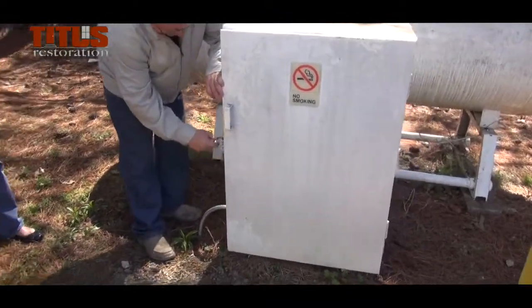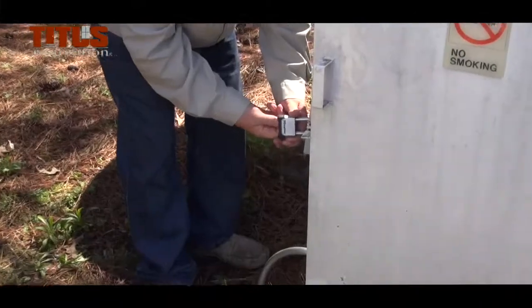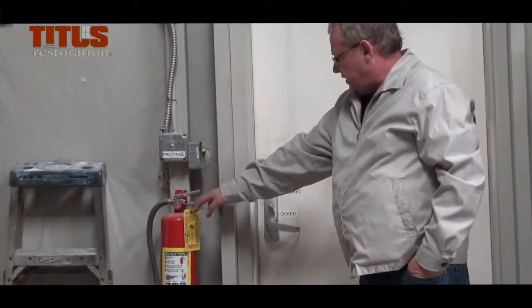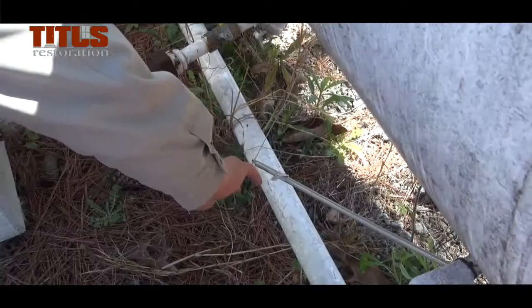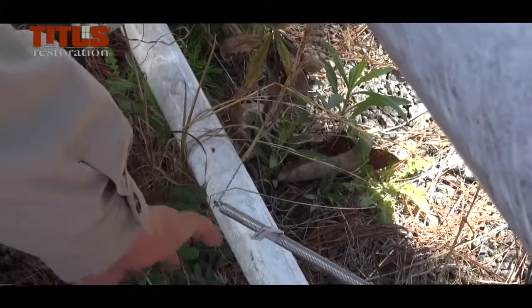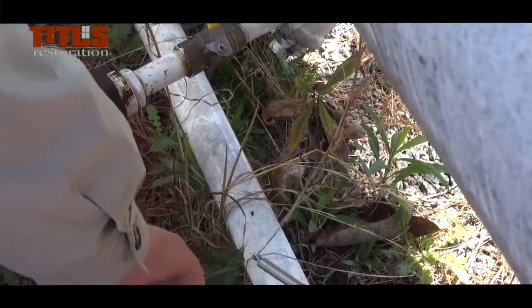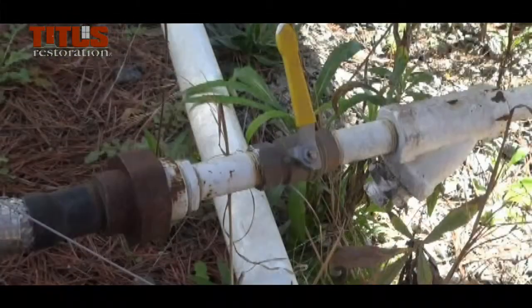If any emergency or dangerous condition occurs, such as fire, explosions, or leaks, you must immediately use one of the shutoff valves: located inside the back door — the light switch; or outside the back door — the red button; or inside the pump — pull the wire; or behind the pump — quick disconnection. If in parallel position the valve is on; if in perpendicular position, the valve is off.